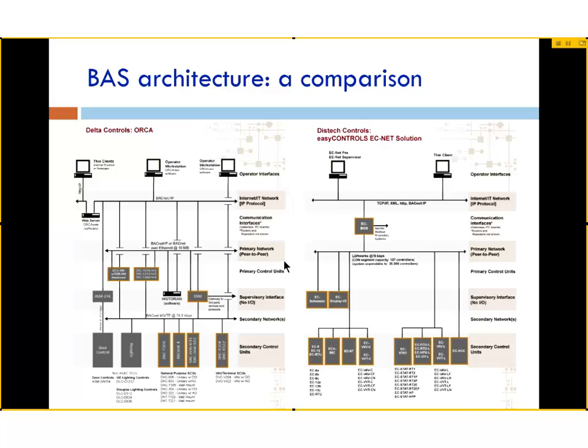Similarly, in the Distech Controls, you have the highest level, and that could be BACnet IP, HTTP, extensible markup language. They have several options there. And then on their primary network, I think they run LonWorks. I can't really see on my screen, but I think they run LonWorks there, and below it's all LonWorks, or peer-to-peer, which is another control protocol, which is a standard in the industry, a competing standard to BACnet. That was developed by the Echelon Corporation in the late 90s. And LonWorks and BACnet for years were pretty much equal market share. BACnet has taken a lead now and is more favored, but LonWorks is the standard in China. And for some industries like train controls now, and others use strictly LonWorks. So a lot of technicians will run into either one of those two protocols, and there are others as well. Next slide, please.